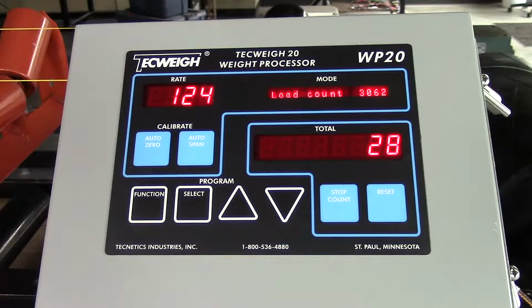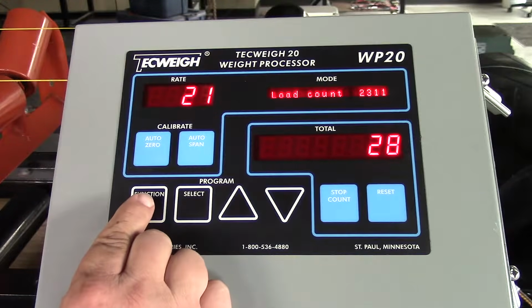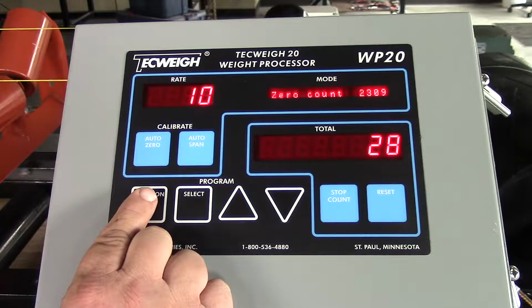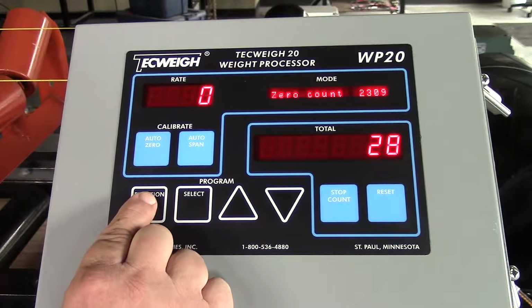And as we remove those weights, the load count goes down, and so does the rate go down. If we move to the next parameter, we'll see the zero count. That shows our zero calibration baseline. And the next parameter would be the span count. That's our span count baseline, or when we put the test weights on there.